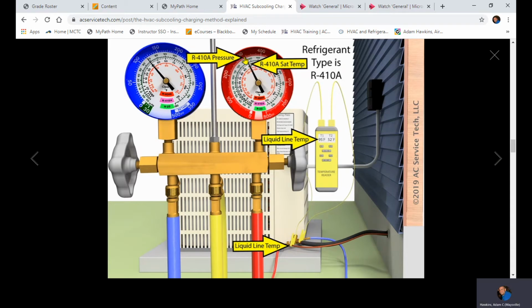It's the same thing we did with superheat. It's backwards. In superheat, your refrigerant temperature would be lower than your line temp. Your line will always be warmer because it's superheated, right? So it's beyond saturation. It's additional heat added. In the case of subcooling, it's actually additional heat removed beyond saturation. So beyond 100% liquid, you got additional heat removed. So if you're using 100 degrees in this example on your gauges and 95 here, your subcooling is 5 degrees. That's how you'd measure that.